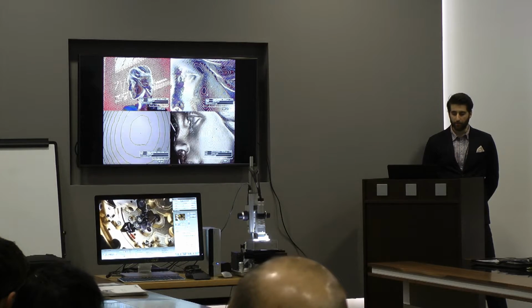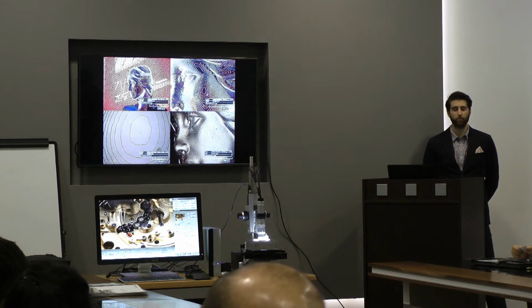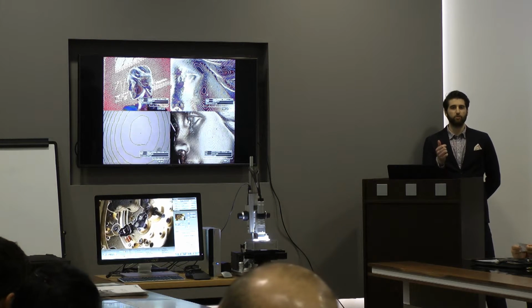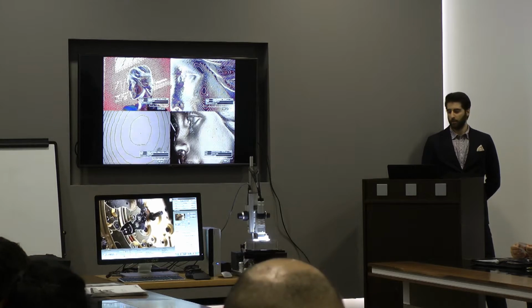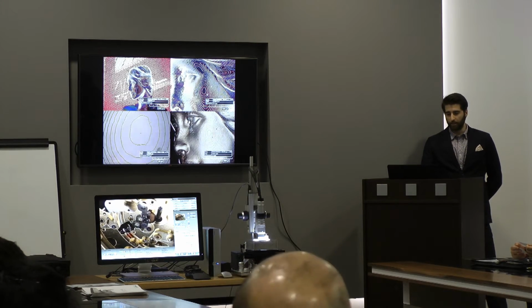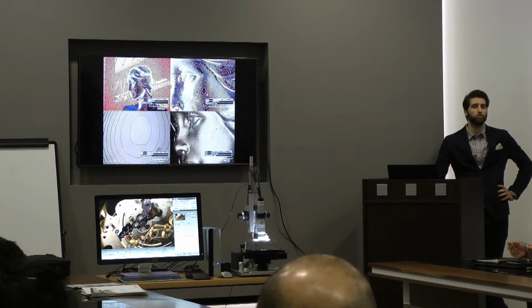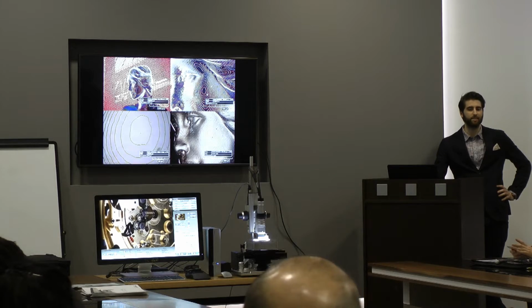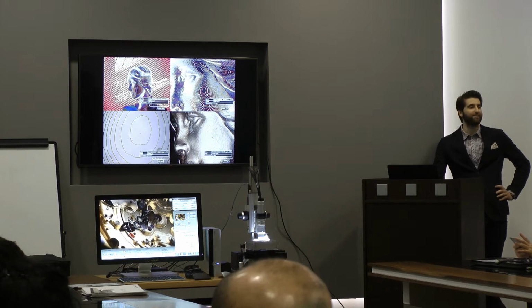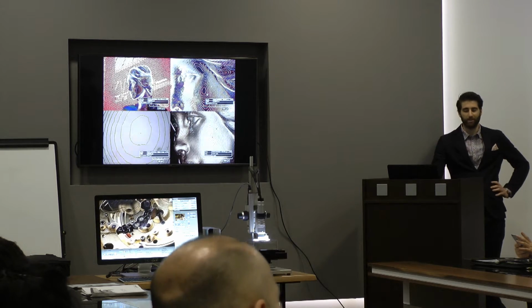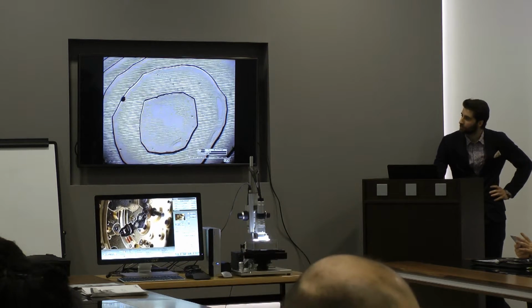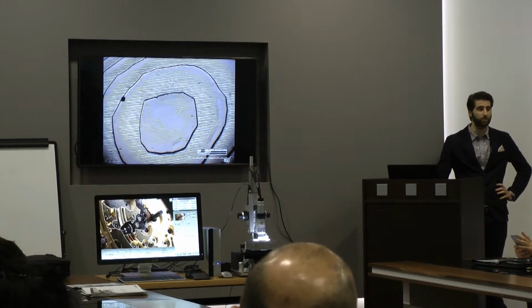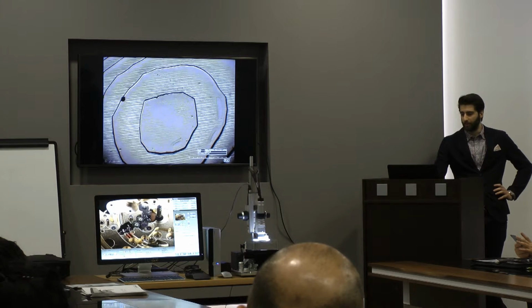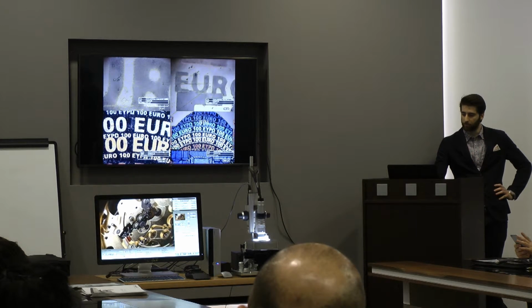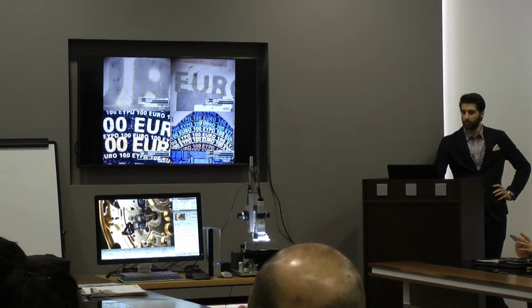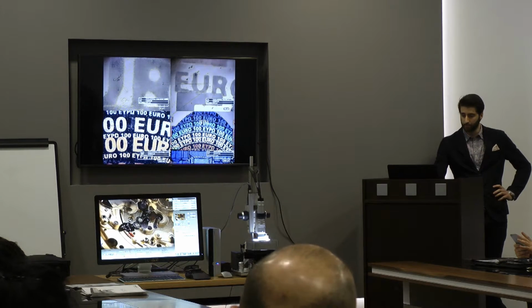And yeah, the most important thing with this is that you can use both at the same time. So you can switch from ring light to coaxial light, but then you can also switch between. So you can give a little bit ring light, a little bit coaxial light. And this is a very unique feature, which gives you the possibility to adjust the lighting to images which are not easy, which are very hard to capture. So if you do this adjustment, you get quite better images. So like this, for example. So here, for example, you can also measure the roughness because you have a lot of details. The first two images are made with coaxial lighting. The lower images are made with ring light.